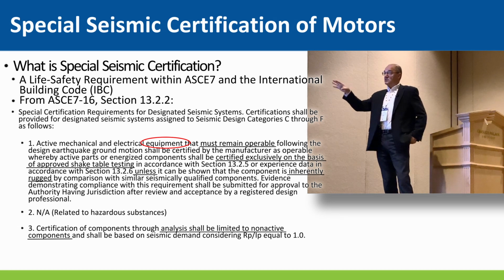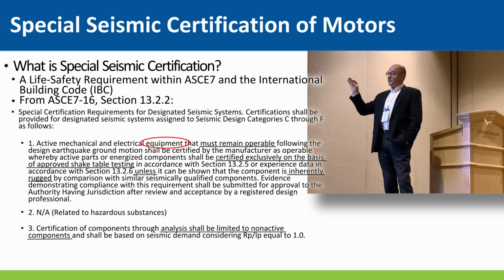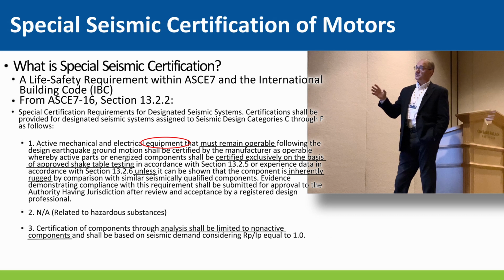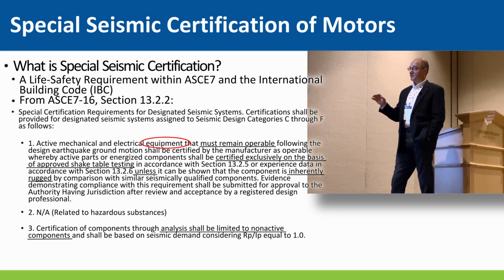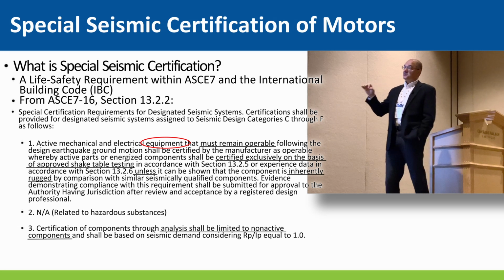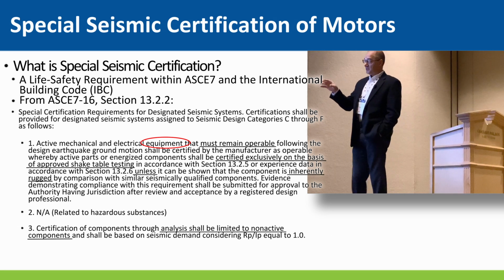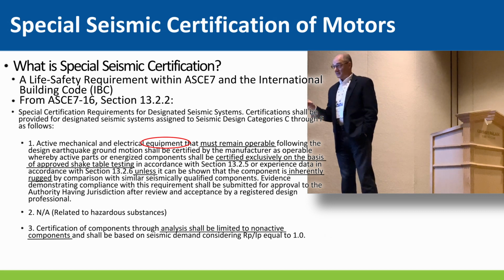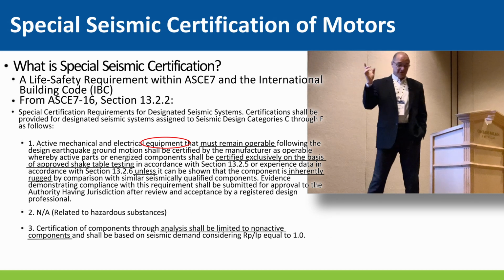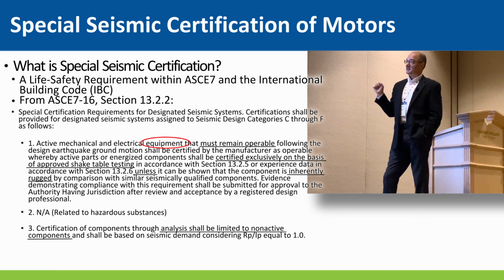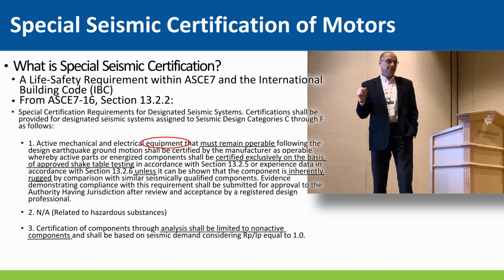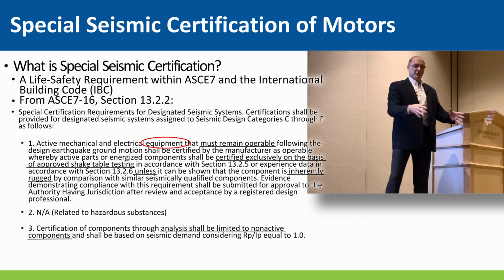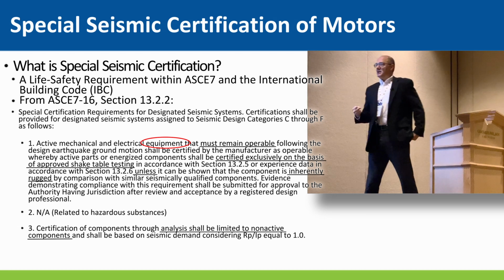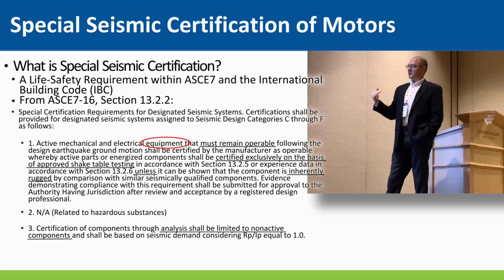So in this code requirement, the equipment has to remain operable. It says, following the design earthquake, ground motion shall be certified by the manufacturer as operable, whereby active parts or energized components shall be certified exclusively on the basis of shake table testing. And this is now where engineers are trying to be lawyers, because in the same sentence, it says, or experience data. Wait, is it exclusive, or do I have an option? So it makes it a little ambiguous as somebody's reading it.